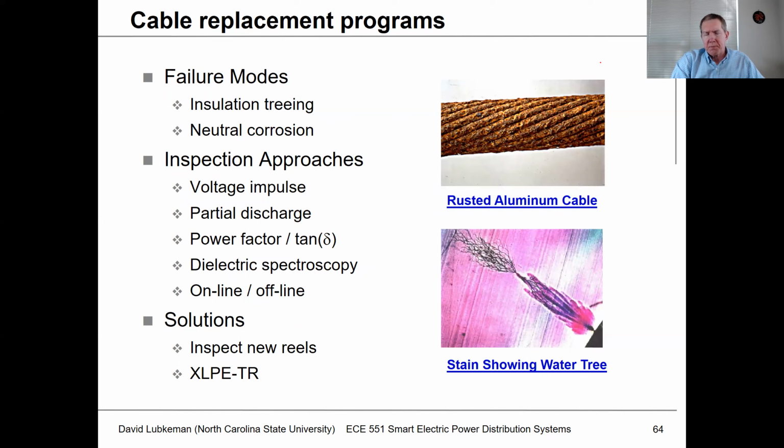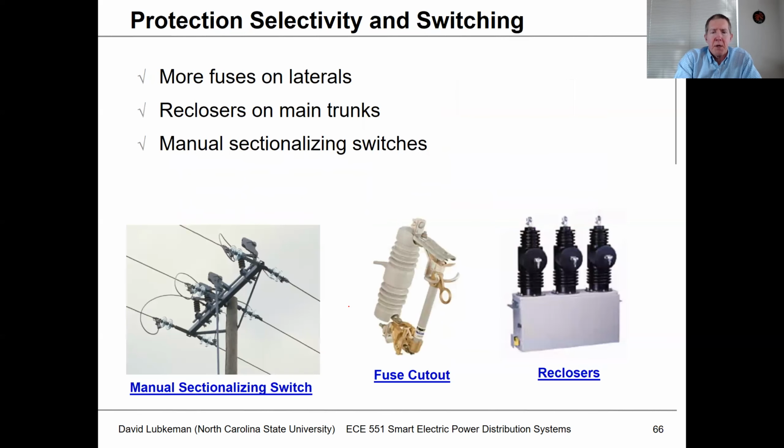And so there's a lot of different things you can do as far as cable and doing some sort of periodic inspection of your cables. You probably wouldn't likely do a lot of this stuff though, unless you were suspecting that certain sections of cables were going bad. If you had brand new cable, you wouldn't be doing this, but as the cable starts to age, you would probably do this more periodic inspection and try to be a little proactive as far as identifying possible problems instead of waiting until the faults occur and the customers complain.